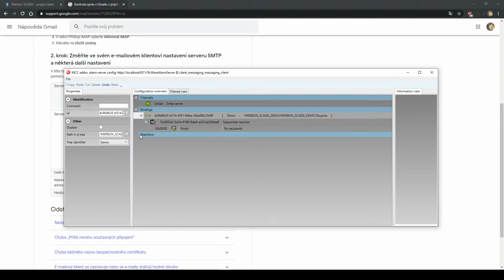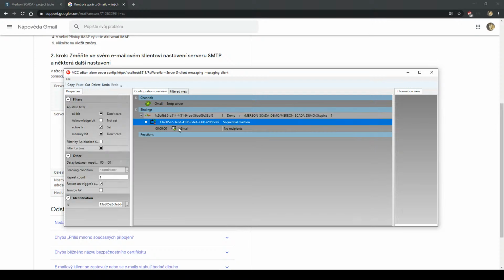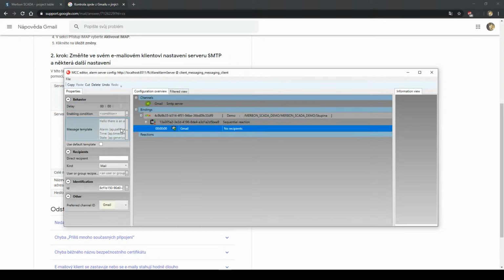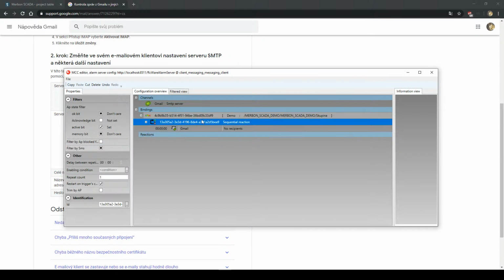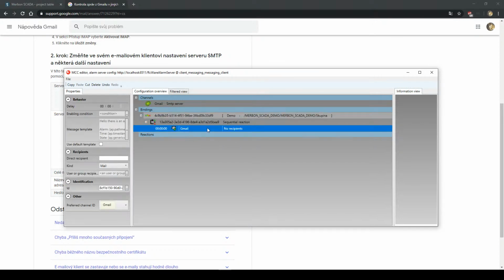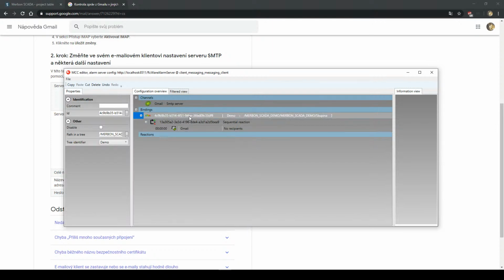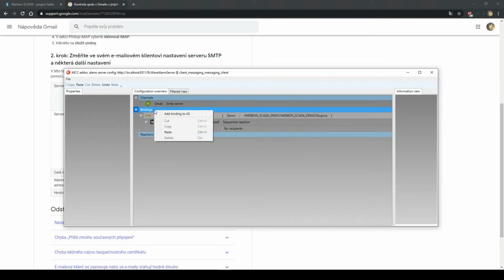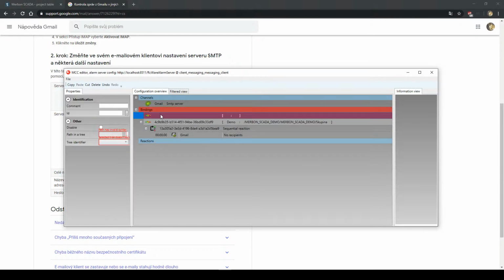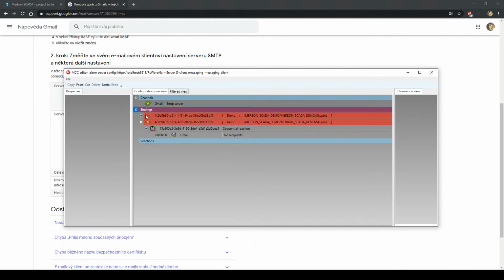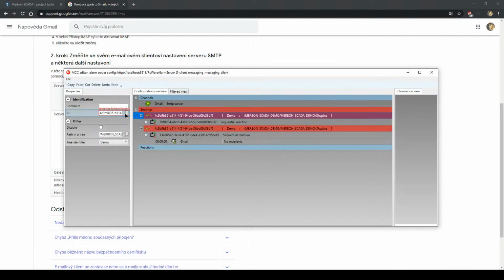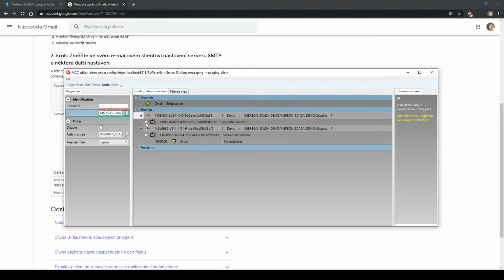If the name of the alarm is enough for you, you can do it like this. So you can have multiple alarm messages with just one configuration. In case you need more alarm points and you have specific names and messages for every alarm, you can use copy here. It's normal Windows Control-C, Control-V, and you just paste it and change the ID here.